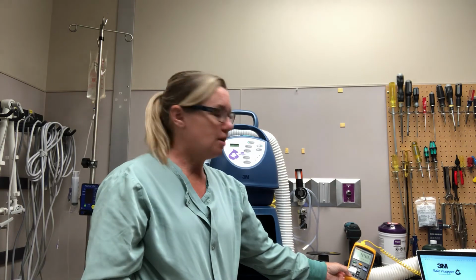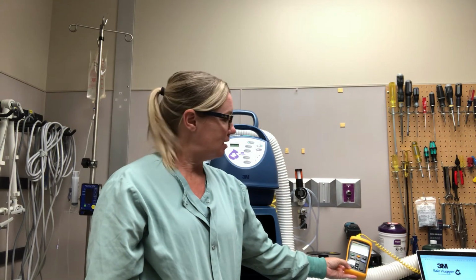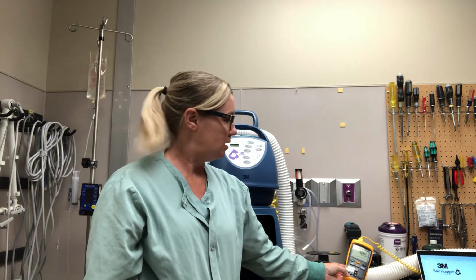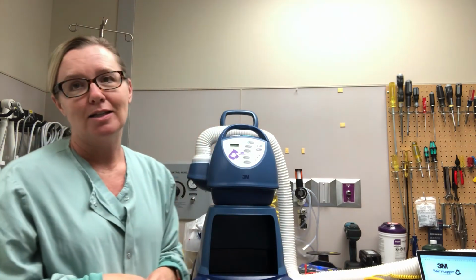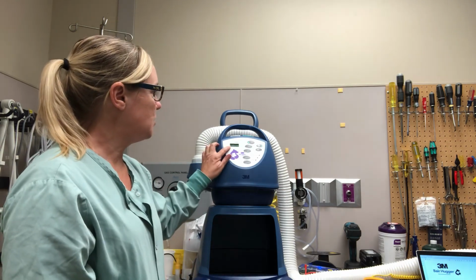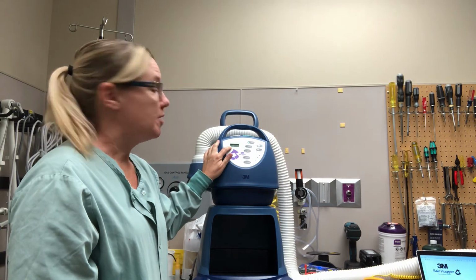This is where I need to look at my meter and see at what temperature my over temp test stops. What's the highest temperature on my meter? It has to be between 46 and 56 degrees Celsius. So we're just going to keep an eye on that. It kind of runs this test itself, and at the end it'll give me an indicator on my little screen saying pass or fail. So we're going to wait until it gets up to the highest temperature, which right there, that was 49 degrees Celsius. So that's well within the 46 to 56 degrees Celsius specifications from the manufacturer. And on my screen it says OT test pass, unplug to reset.